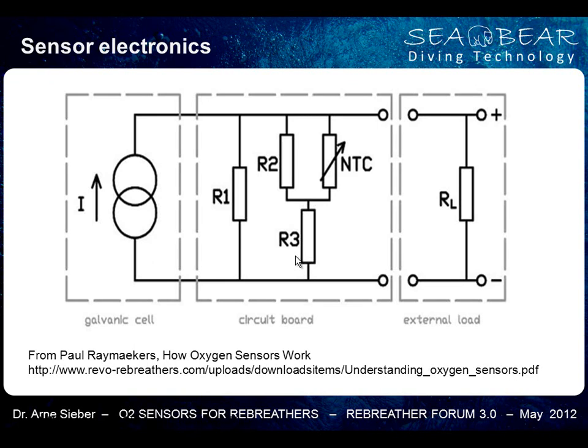I think you can download it from his webpage. This shows how the sensor deals with these temperature changes. The sensor is a current source, so we measure electrons. Here we have a network of resistors and a temperature sensitive element, an NTC. With this kind of network, we can achieve temperature compensation, so ideally this type of sensor will always produce the same millivolt signal, independent of the temperature it's under.